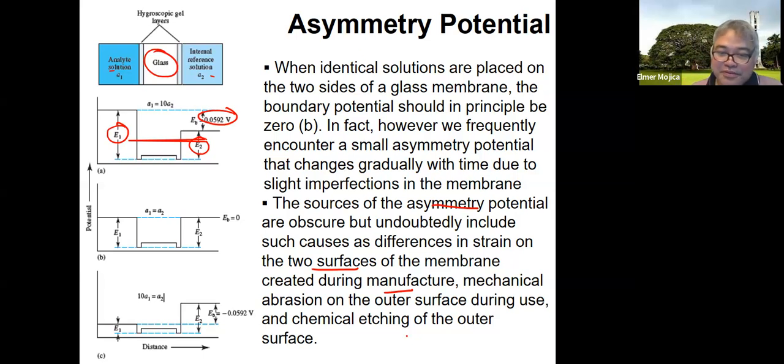You need to do a calibration. You have to calibrate it with one or more standard or analyte solutions. You have to do this calibration every day, and more often when the electrodes receive heavy use. That's the way to at least overcome this imperfection.